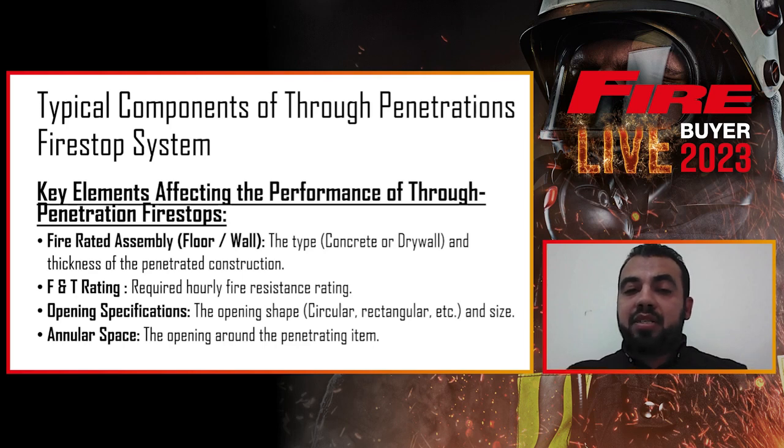In this case, the annular space has a limitation on the minimum and maximum and needs to follow what your system gives as limits. Exceeding the limit or going for zero annular space should be within the acceptance of the tested system, as per the data sheet or the drawings provided by the firestop system manufacturer.